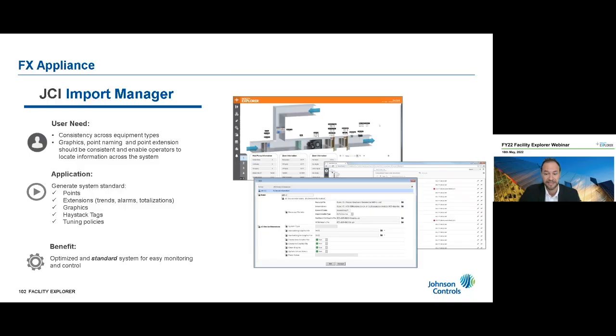The Import Manager automatically creates the database for the devices and all associated points. It also automatically adds point extensions such as trends, alarms, and totalization. More importantly, it automatically generates default graphics for the systems — here's an example with the new graphics coming this summer, and those graphics are fully editable if you want to move things around. This gives a good head start with graphics, saving time. It also automatically adds tags to the points, which we'll discuss in more detail later, and finally it automatically tunes our BACnet network, assigning appropriate tuning policies, which is important to optimize the network and avoid communication issues.